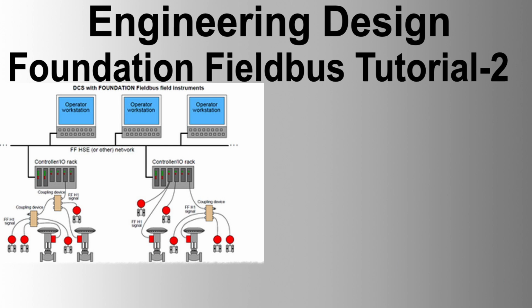Link and schedule. A measurement or control application consists of function blocks connected to each other. These connections are made through link objects in the function block VFD. A link object connects two function blocks within a device, or a function block to a VCR for publisher or subscriber. The system management and data link layer cooperate to orchestrate the execution and communication of function blocks even when blocks are distributed among devices.